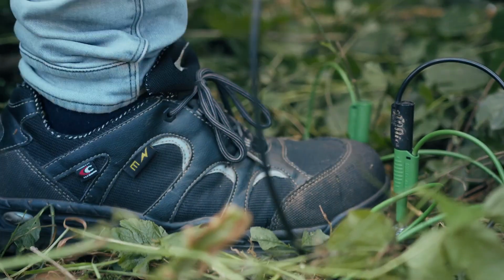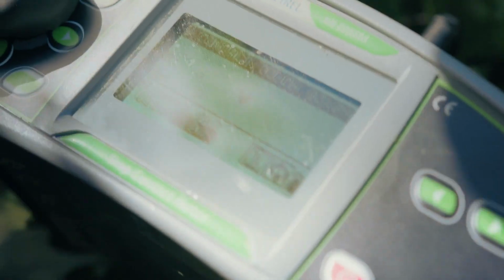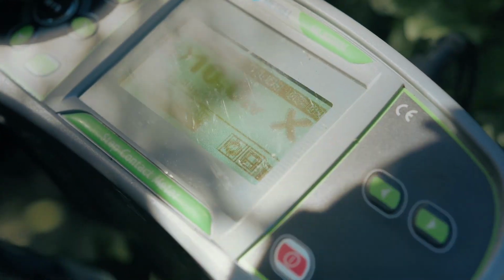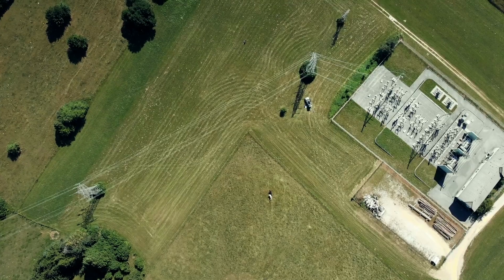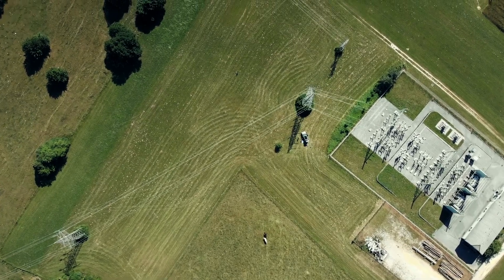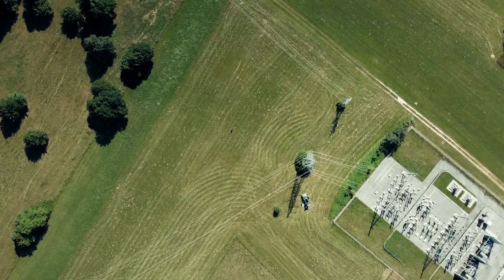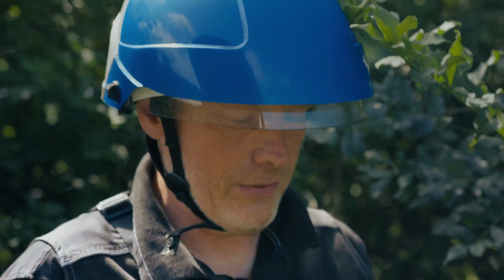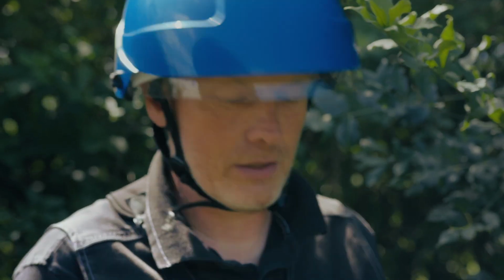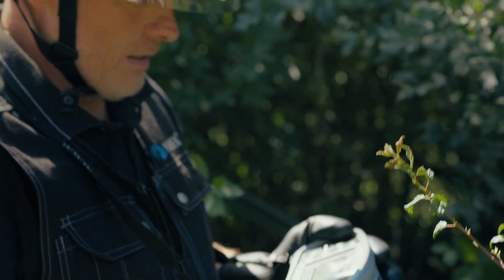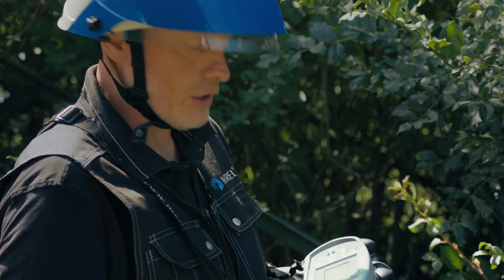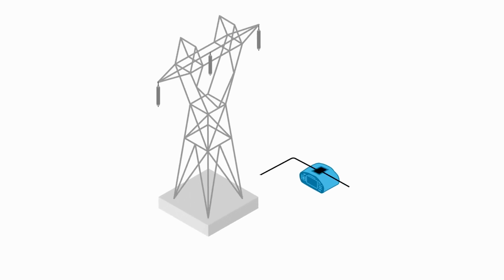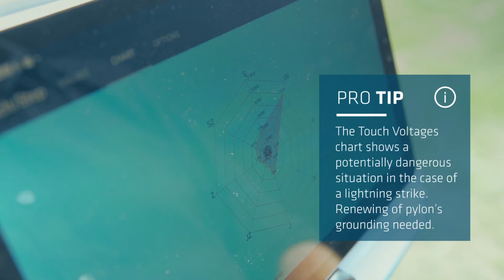We need to step on the plates first, and we can see the result is between 8 to 10 kilovolts, which is very high for this situation. So we have quite a dangerous situation in the case of lightning strike, which means that this part of the pylon needs to be repaired and adjusted, especially when the solar power plant will be built in this field. We need to redesign the complete grounding of this platform. This was the touch voltage measurement, which is usually the most dangerous or extreme situation, if somebody is touching the pylon during the storm. Next, we will disconnect from there and measure the step voltages further on.